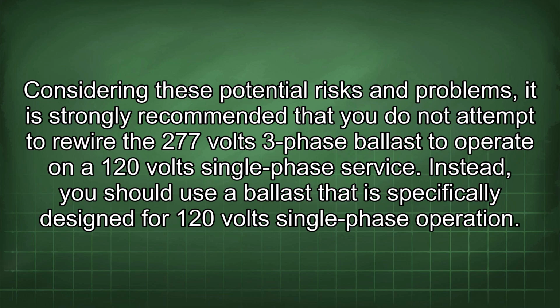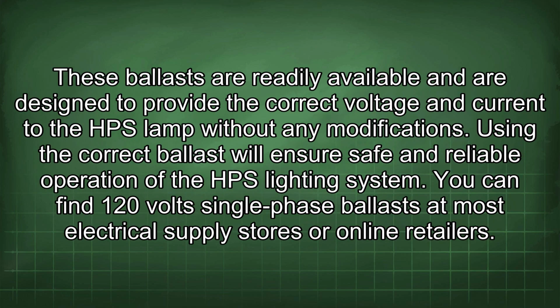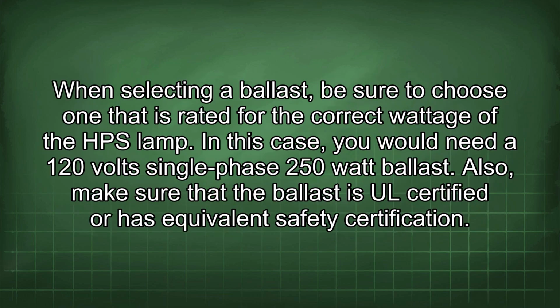Considering these potential risks and problems, it is strongly recommended that you do not attempt to rewire the 277 volts 3-phase ballast to operate on a 120 volt single-phase service. Instead, you should use a ballast that is specifically designed for 120 volts single-phase operation. These ballasts are readily available and are designed to provide the correct voltage and current to the HPS lamp without any modifications. Using the correct ballast will ensure safe and reliable operation of the HPS lighting system. You can find 120 volt single-phase ballasts at most electrical supply stores or online retailers. When selecting a ballast, be sure to choose one that is rated for the correct wattage of the HPS lamp. In this case, you would need a 120 volt single-phase 250 watt ballast.